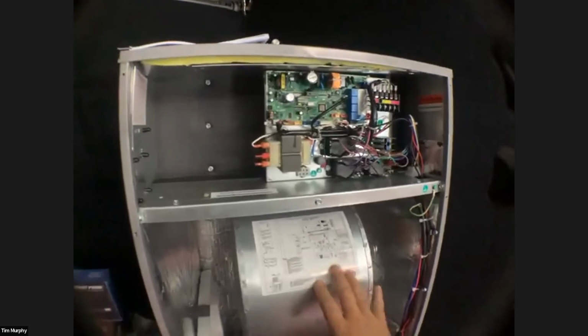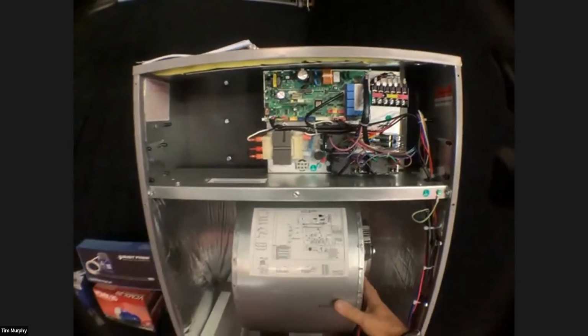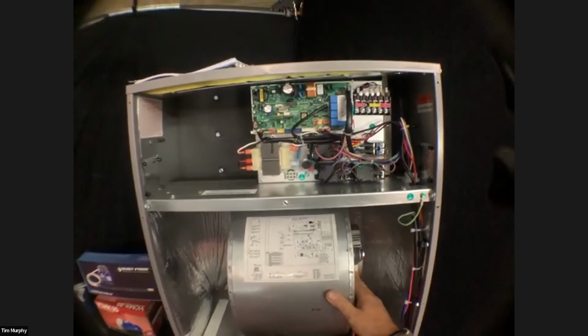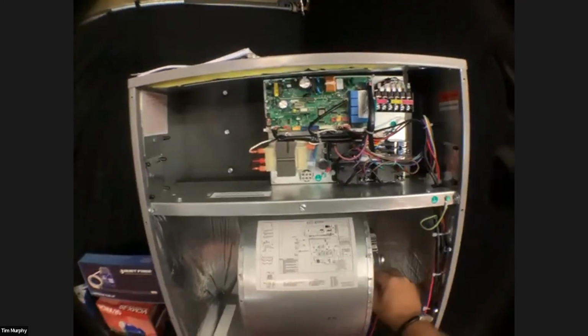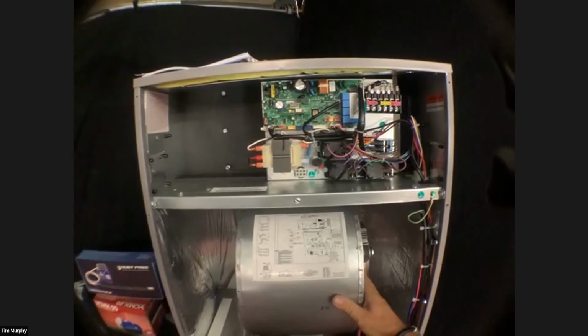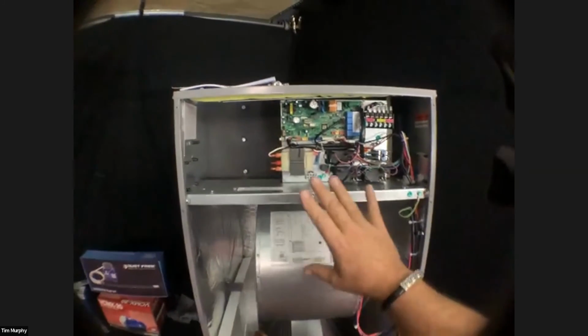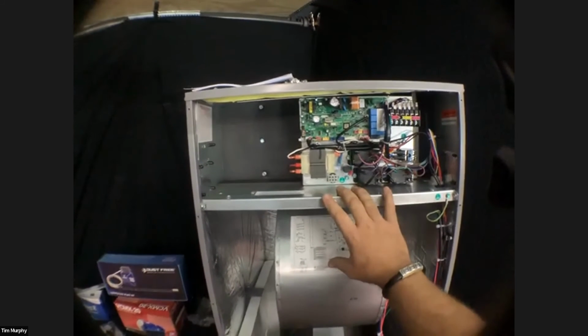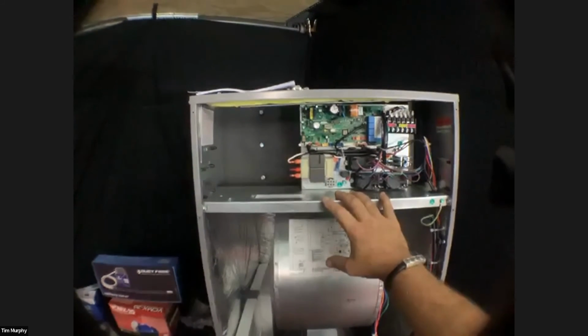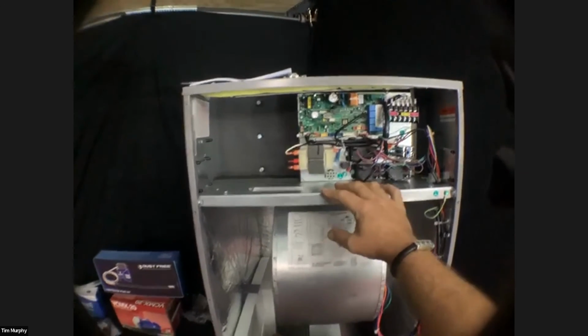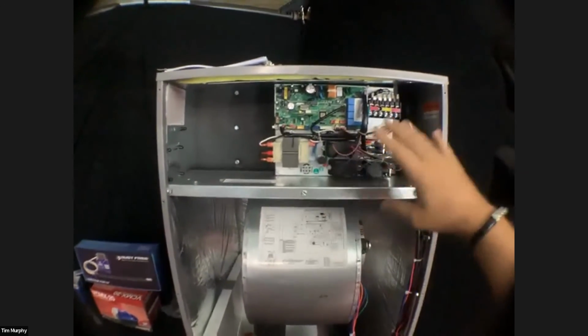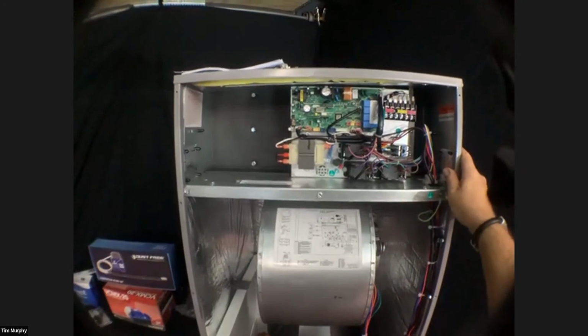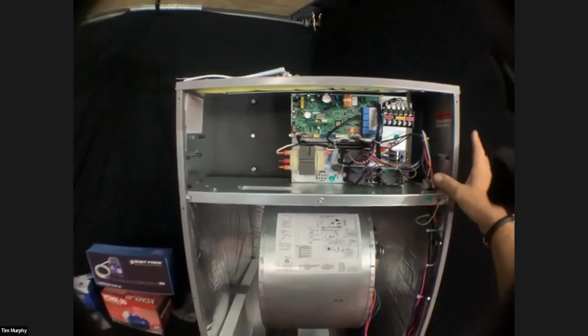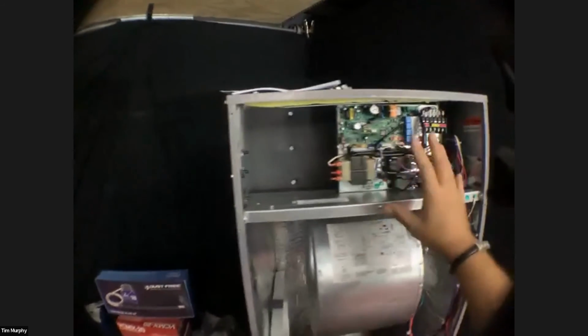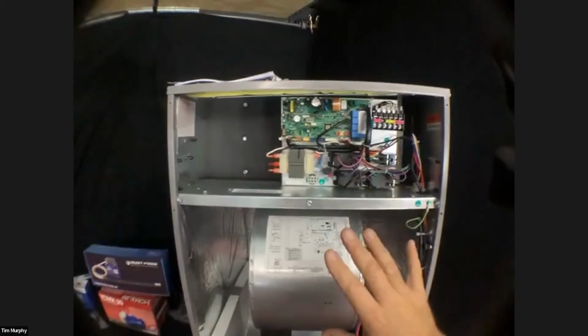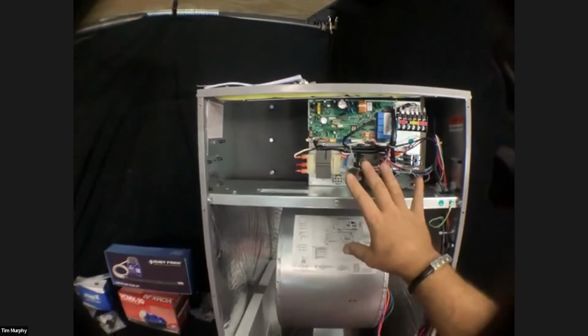You get your schematic and basic information telling you your fan speeds. There are fan speed settings, and if you need to, you can change them depending on the static. I will tell you that this is the 3-ton system, which I believe is rated up to one inch of static pressure. The 12, the 18, the 24, and the 30 are 0.8, I believe. And Michael, if he's on there, maybe he can double check me on that. That's important if you're going into a high static course.